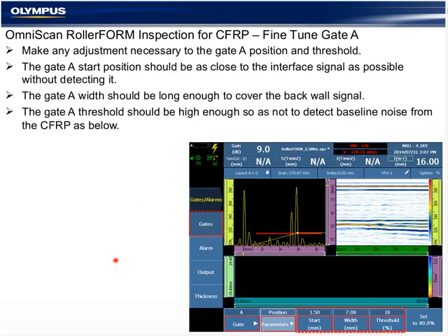Okay, we're going to optimize our gate. The gate is available from the touch screen. If I touch the gate in this area here, I will get the start in the upper left-hand corner. In the middle, I will receive the threshold, and tapping the gate on this end, I can adjust the width. These are displayed here under the gate submenu. We want to put this gate as close as we can to the interface so we don't interfere with the inspection. Putting the gate too close to the interface will generate red pixels of the shallowest readings throughout our C-scan. This can be changed in analysis mode after the inspection at any time because all A-scans are saved.